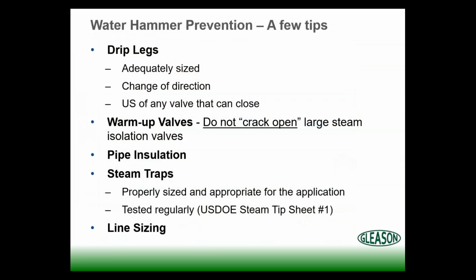And so just a few tips to consider when we're thinking about how to prevent water hammer in our steam systems. Our drip legs must be adequately sized. We'll talk more about that here in a second. Any change of direction in our steam lines, left, right, or up, we want to put an appropriate sized drip leg. And we also want to put drip legs in upstream of any valve that can close, regulator, control valve, isolation valve, whatever it is. If that valve can close, we want to put a drip leg upstream of it.